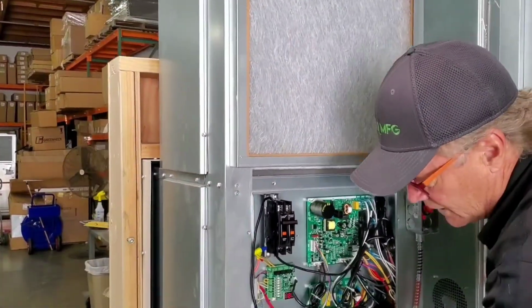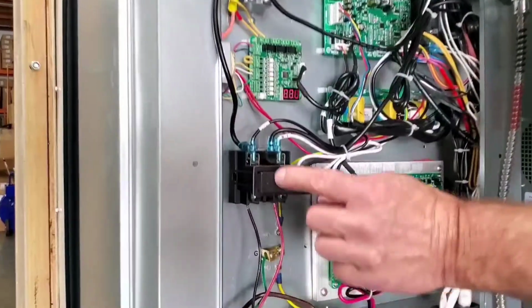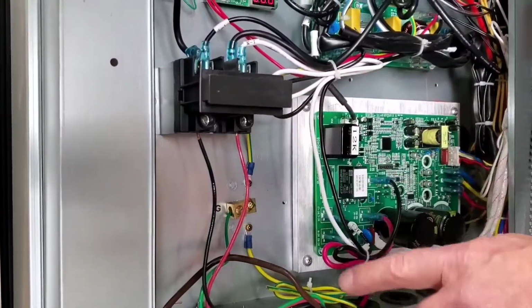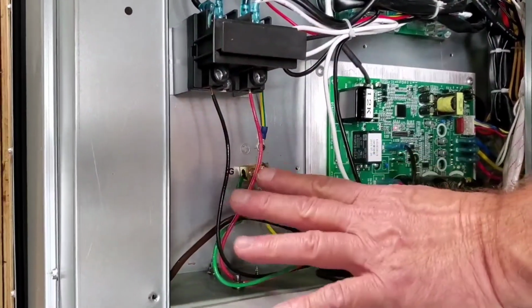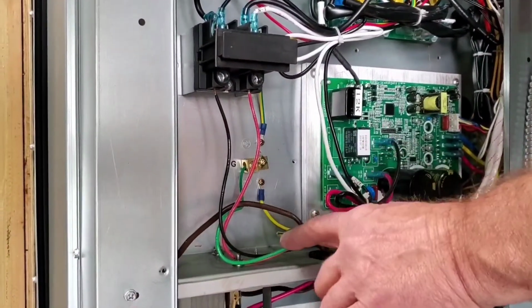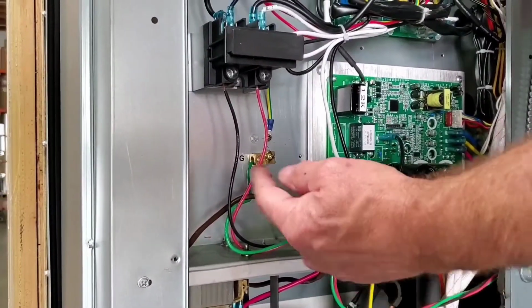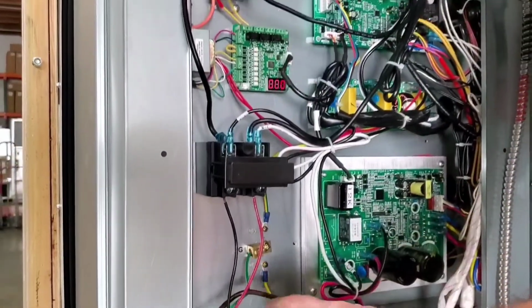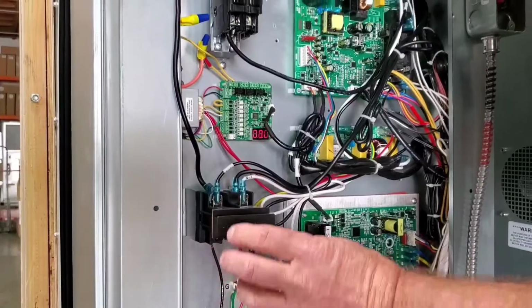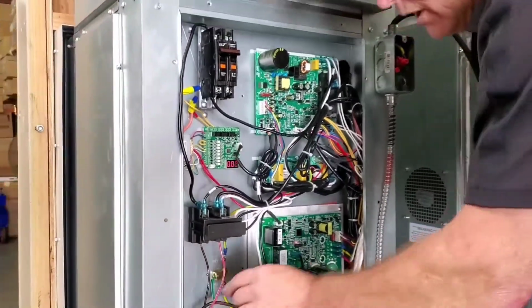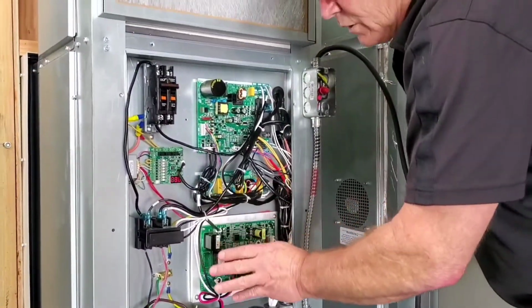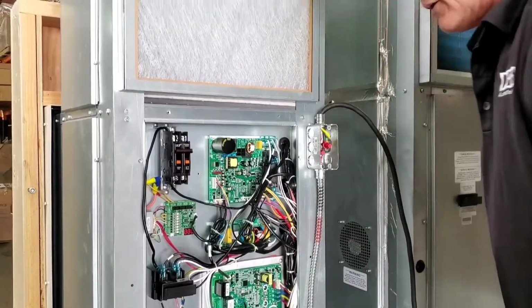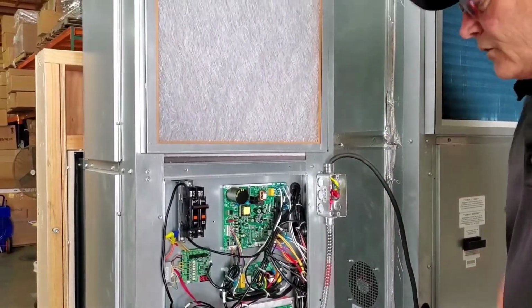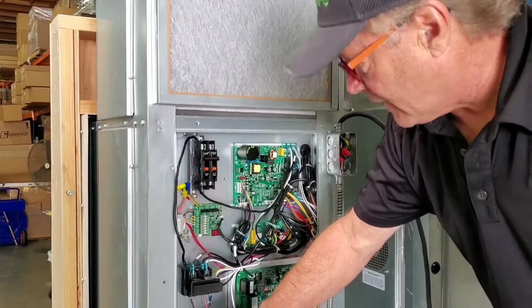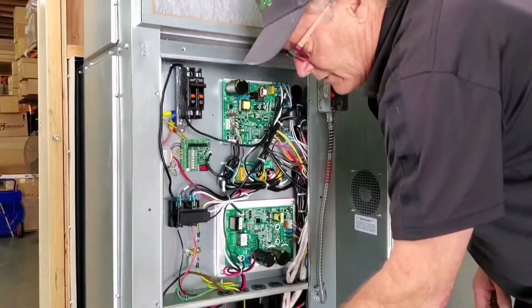So once you bring in your line voltage, connect your 2 hots to the line 1, line 2. If you're using a white wire, and this is 10 gauge wire by the way, if you're using a white wire, tape it with color. Make it red or black, yellow. Anything coming into a piece of equipment needs to be color, not white. White is neutral. White inside of a unit has already been UL'd, so it can be whatever color that UL is allowing it to be from the manufacturer. So that's your line voltage tie-in. Now, then your low voltage tie-in is coming in right here.